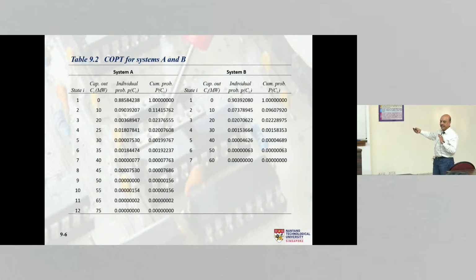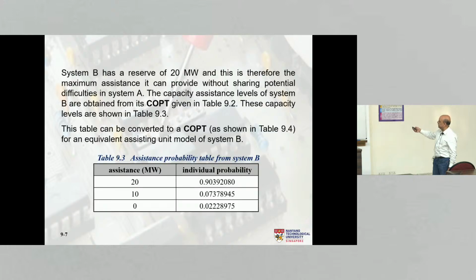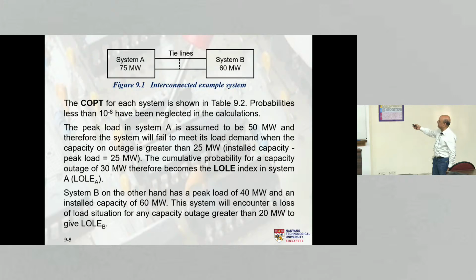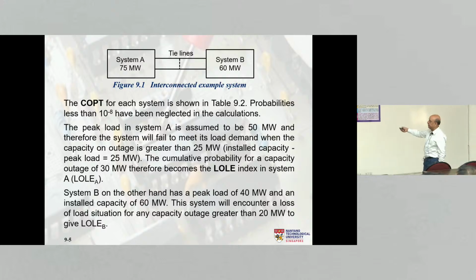So any outage more than 20 megawatt is going to lead to loss of load in system B. So up to 20 is fine. This is the cumulative probability, 0.00158. So you see that the risk in the two systems is very different, right? So system B risk and system A risk. So LOLE index in system A is the cumulative probability for capacity outage of 30 megawatt. Similarly, LOLE in system B is the cumulative probability of any capacity outage greater than 20 megawatt. Okay, so we know the numbers there.